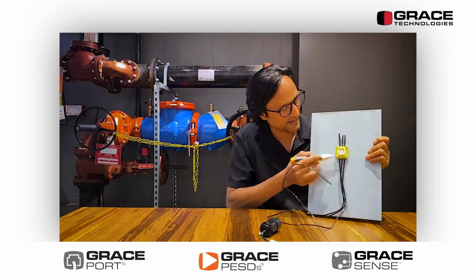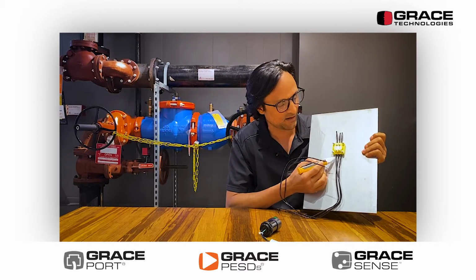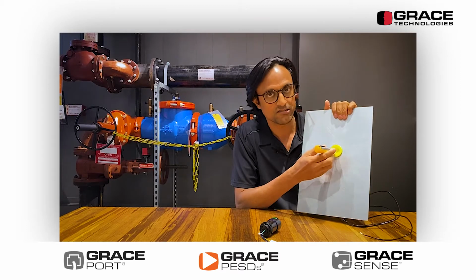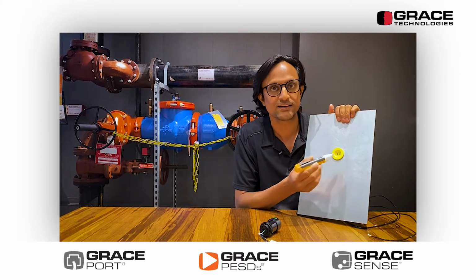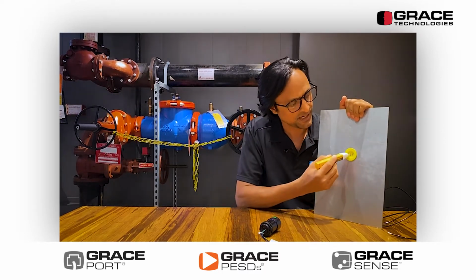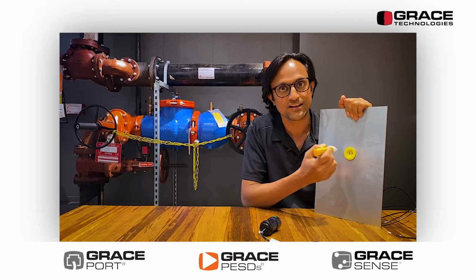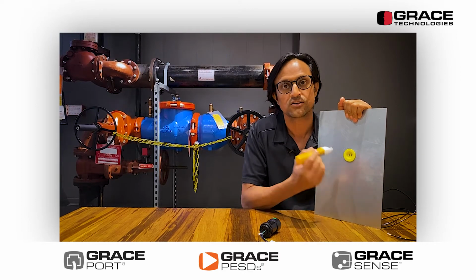So as you look on the back side of this, we are passing through 3 wires through this device. So basically, you can take L1, L2, L3, you can pass it through this device, and then as you pass this, you can verify this voltage using the detector pen. If there is a voltage present at any of these 3 leads, this detector pen will still pick up between these 2 slots because these 2 slots have been positioned in such a way that it will pick the voltage between any 3 phases as they pass through this device. So that's the one thing.